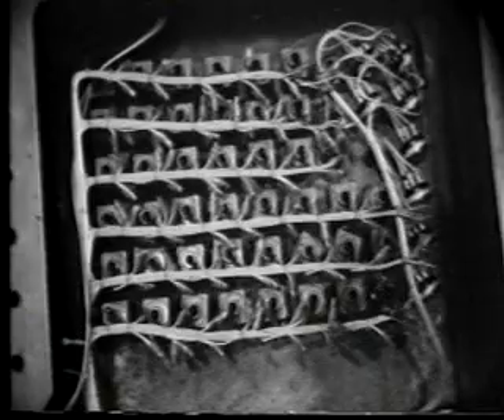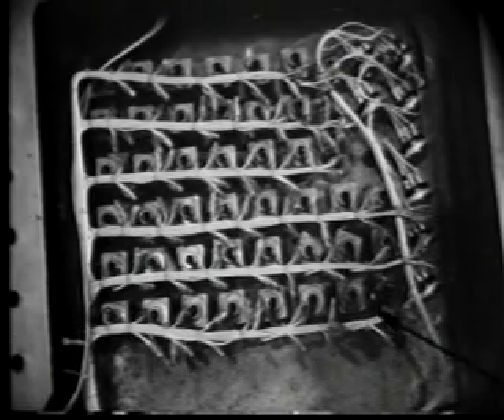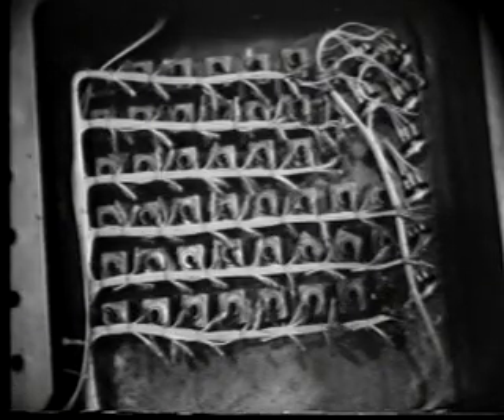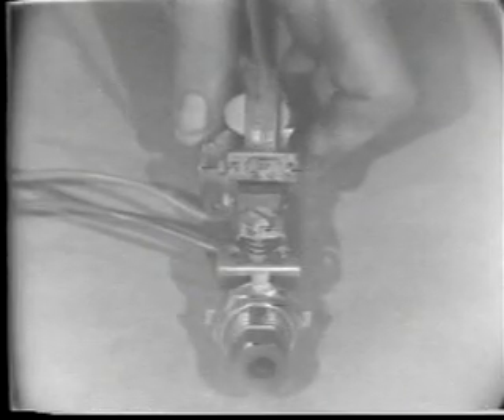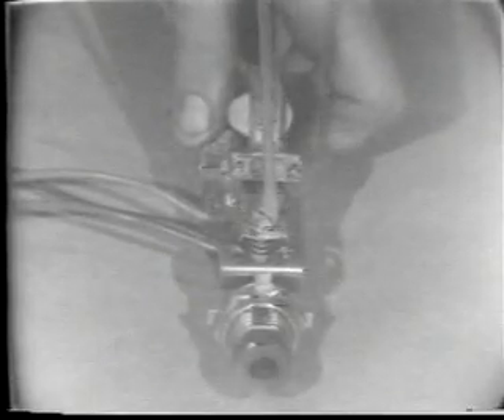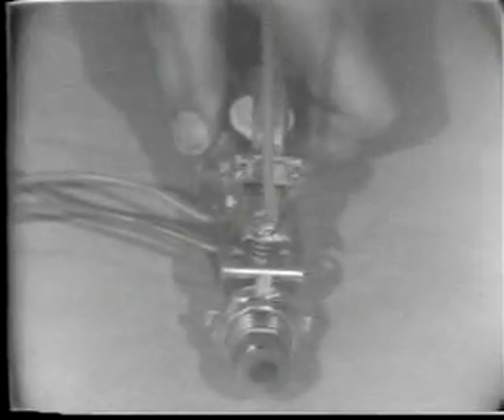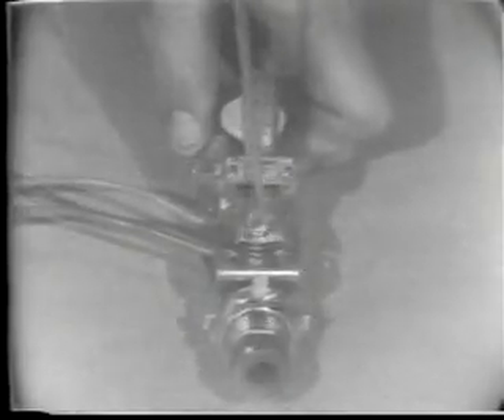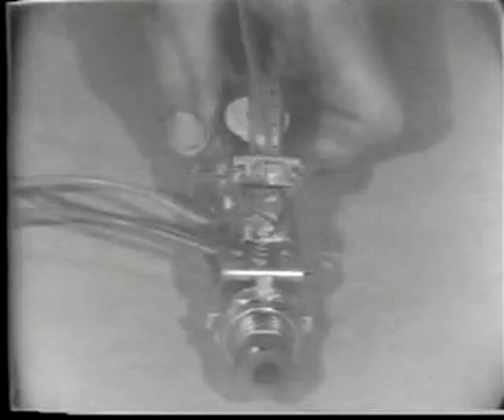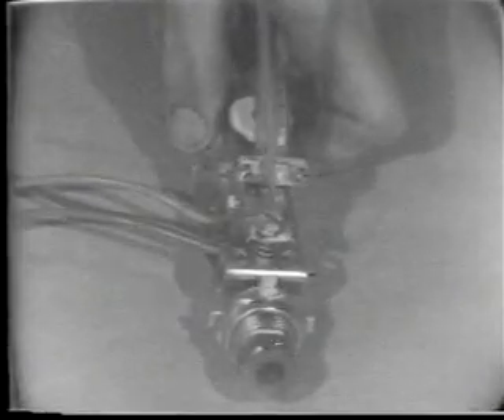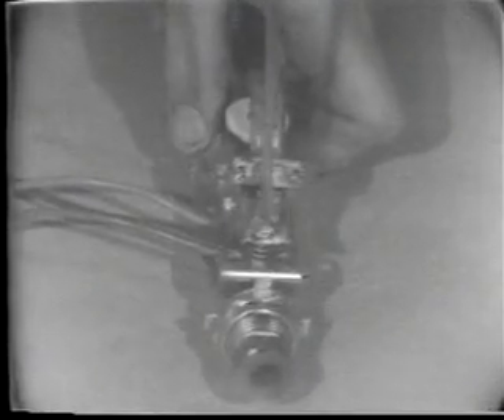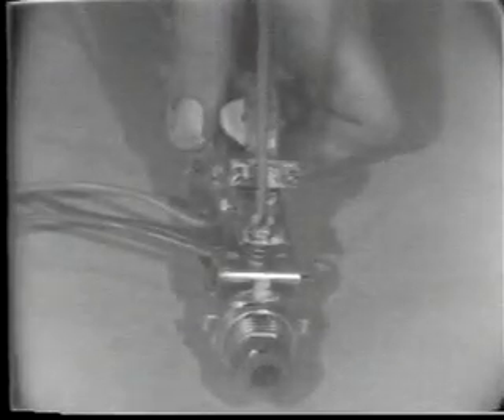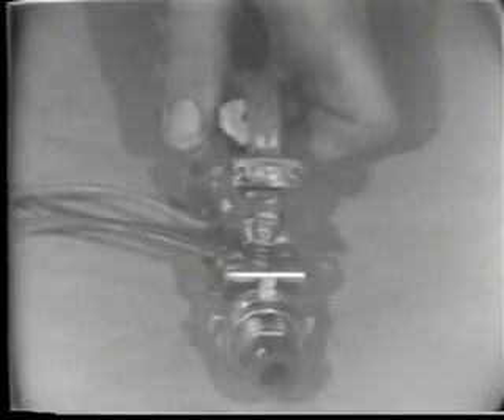Another use for the pressure switch is for the low accumulator pressure alarm. The purpose of this switch is to blow a horn at the driller's panel and to turn on a warning light at the mini remote panel. This is an adjustable pressure switch which may be set to any desired pressure. This is done by rotating the adjusting screw counterclockwise to have the alarm sound at a higher pressure and clockwise to have the alarm sound at a lower pressure. The gray knurled knob is used to adjust the span or differential.